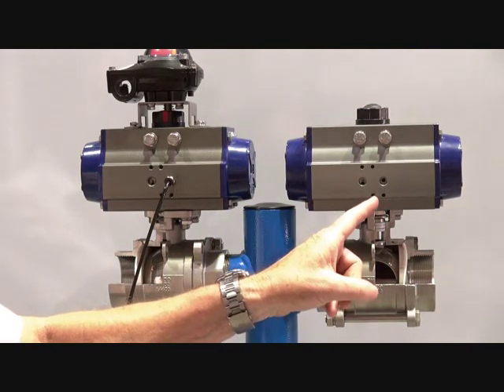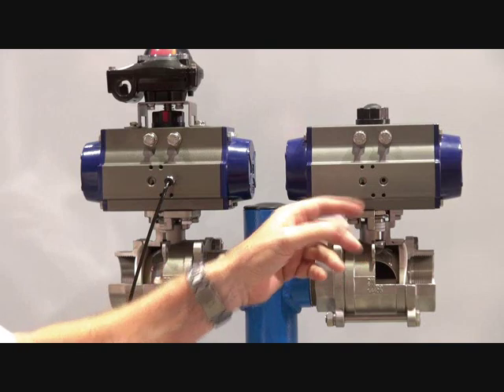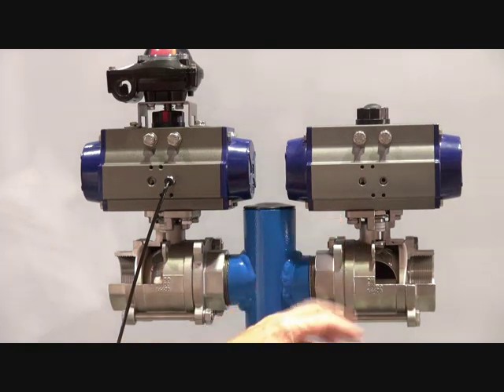Double acting means that we can put air on one side, the unit will rotate in one direction. Air on the other side and the unit will rotate back again. Remove the air and the actuator stays in position.